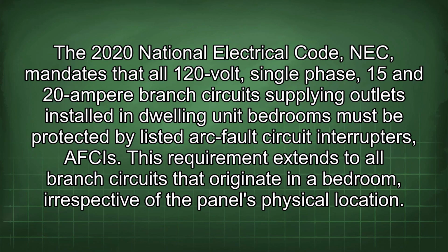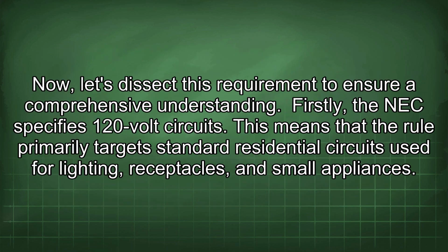The 2020 National Electrical Code (NEC) mandates that all 120-volt, single-phase, 15 and 20 ampere branch circuits supplying outlets installed in dwelling unit bedrooms must be protected by listed arc fault circuit interrupters, AFCIs. This requirement extends to all branch circuits that originate in a bedroom, irrespective of the panel's physical location. Now, let's dissect this requirement to ensure a comprehensive understanding.